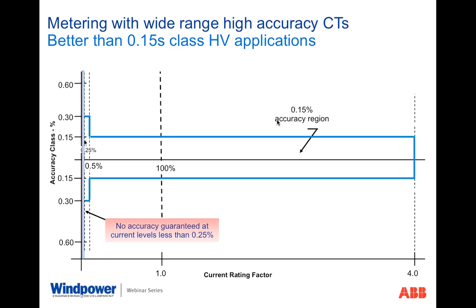It would also measure in the same 0.15 accuracy all the way down to 2.5 amps on the primary. So as you see, we're giving the owner of the farm the accuracy he needs. We're also giving the connected utility the accuracy that they demand to be able to meter their power flow back into the wind farm application. And even at that point, we're splitting hairs down here below 0.5%.